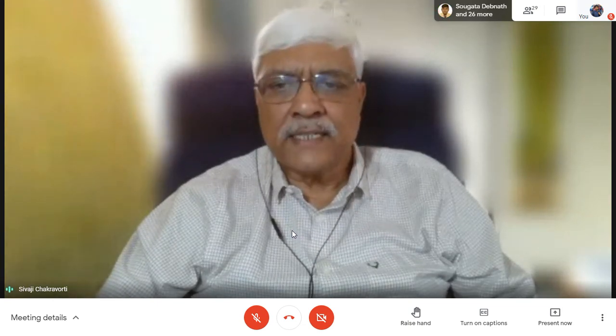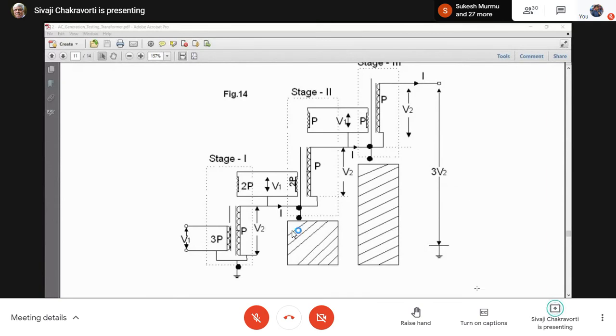That is this schematic diagram. So again, you can see here that these blocks, rectangular blocks, these are the insulating blocks. As I go higher up on the cascade connection, we have to put it on bigger and bigger insulating structure. This is number one. But this can be done, as I have shown you. Then the question is fine, but then the primary of the second transformer, how does it get its power? Well, it gets from the tertiary of the first transformer.